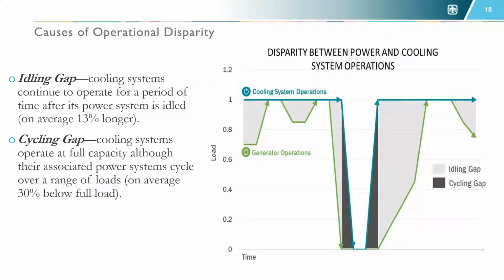You also see another thing going on here in these darker gray areas - that's where at various times the generator is taken all the way to zero, idled. It could be that the load is gone and you need to shut it down, or it could be shut down for maintenance. But there's always a period of time where the cooling system is still operating while the generator is taken down to idling, and there's a good reason for that.